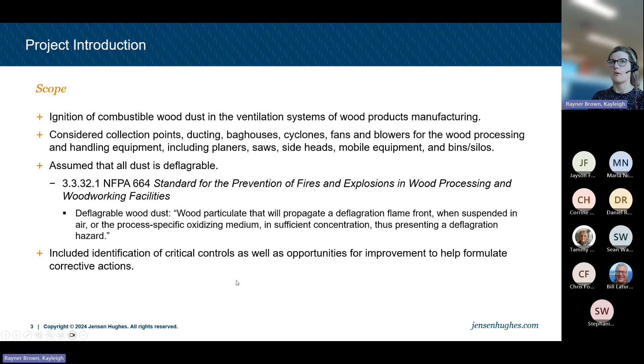What was the motivation for this project and for this work? It's the fact that ventilation and dust collection systems in facilities are a major concern. Dust collectors are one of the highest hazard areas in facilities handling combustible dust, due to their inherent nature and design. We have suspended dust within enclosures, interconnected within the process and throughout the facility. There's also a lot of opportunity for ignition sources like static electricity and ignitions from mechanical failure. Deflagrations, because of that interconnected nature, can easily propagate throughout ventilation systems if there is a lack of effective ignition source control and explosion protection, like deflagration isolation.